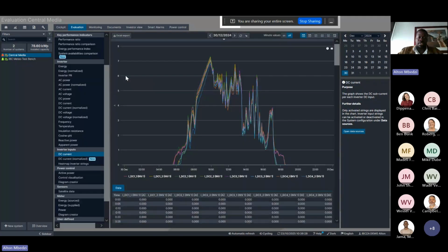We do have DC string or inverter MPPT monitoring, which, as you can see here, I have my inverter input, and then I can see from inverter 1, DC number 1, it's 1, 2, 3, 4 strings on this specific inverter. You can see, there it is - I can see my currents, everything is actually perfect. The other one was down, you probably have to check your fuses. So the DC string monitoring side of things is available.